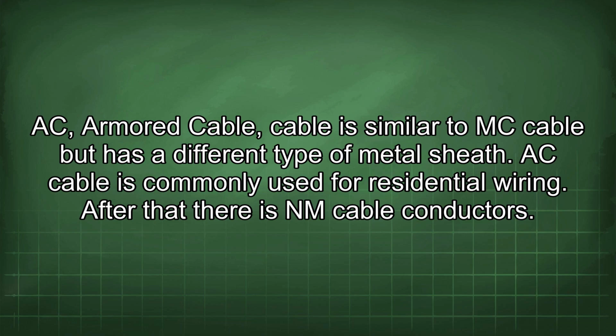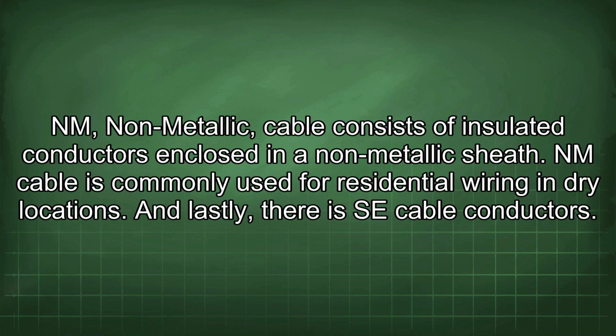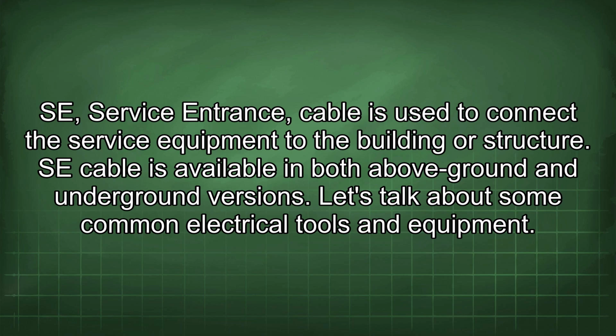After that there is NM cable conductors. NM, non-metallic, cable consists of insulated conductors enclosed in a non-metallic sheath. NM cable is commonly used for residential wiring in dry locations. And lastly, there is SE cable conductors. SE, service entrance cable, is used to connect the service equipment to the building or structure. SE cable is available in both above ground and underground versions.